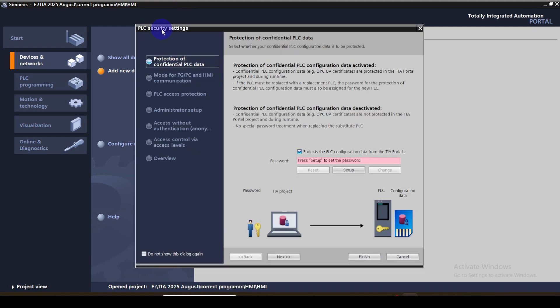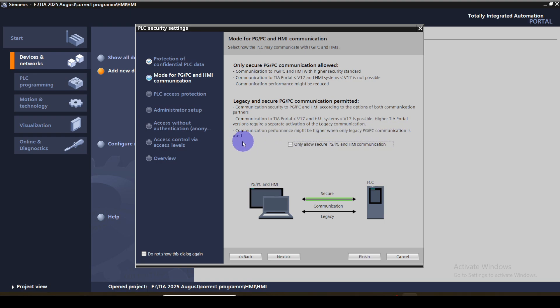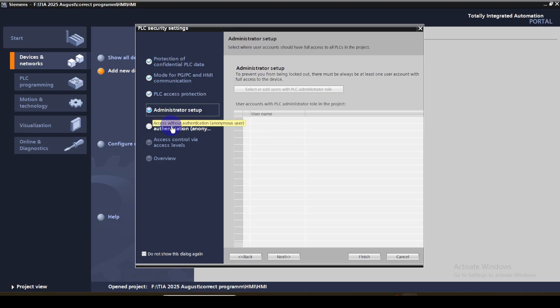Initially we need to set the PLC security settings. First, the protection of the confidential PLC data — you can give a custom password to protect the configured data of the PLC. For this project, I am not going to give any password, so I am going to uncheck this one. For PG, PC and HMI communication, I am going to uncheck the secure communication option and also uncheck the legacy PG/PC communication option. For PLC access protection, I am going to disable the access control so anyone can access the PLC. For this project, we don't want access control.